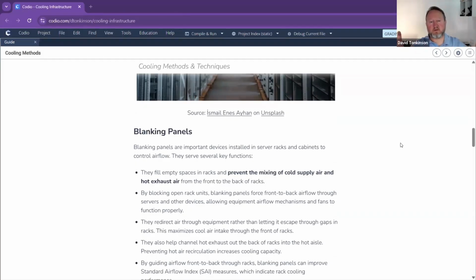They're normally single U, so you will have multiple blanking panels. When you want to install a server, you take out this piece of plastic, and don't throw it away, put it on the floor, and then you slide another server in there. The reason that's done is because we don't want the air to move around inside that rack unless we are pushing it. Unless it is doing useful stuff such as cooling our servers, we don't want it to move anywhere. Most servers, well, all servers and all switches are closed boxes.